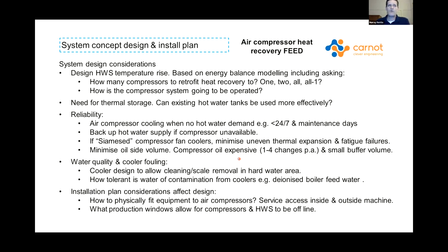We've talked about the water quality and cooler fouling. Stefan did as well. Are you designing for a hard water area or are you designing for a soft water area? You will get scale buildup. A lot of compressor companies, the OEM systems, won't sell a system if it's going to be heating the water above 80 degrees because they're scared of scale buildup inside the machine. So you need to design your system. If you're going to get scale, how are you going to get rid of that scale and keep your system working properly? Or are you going to just replace the coolers? Are you going to try and clean the coolers? Are you going to do both coolers, one cooler? So there's a lot to consider in that respect.